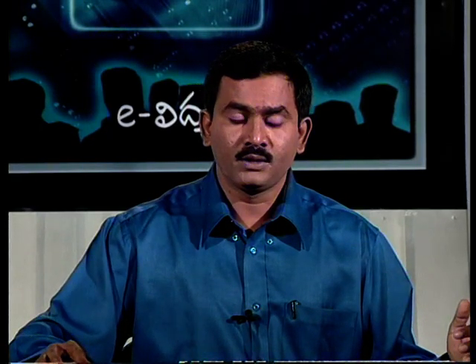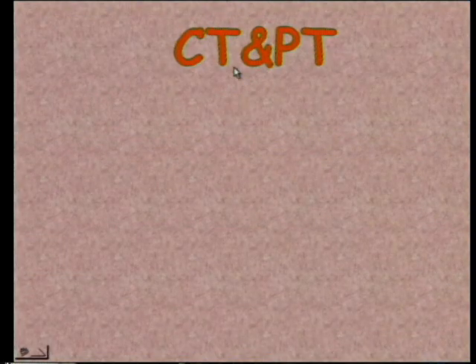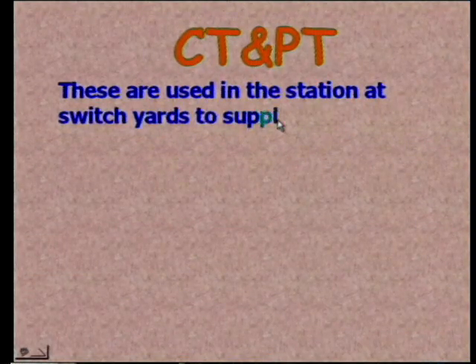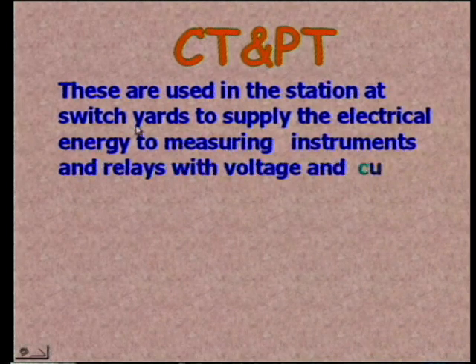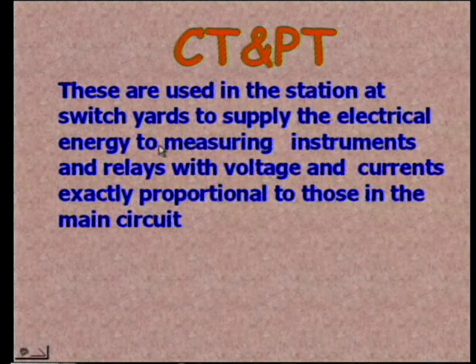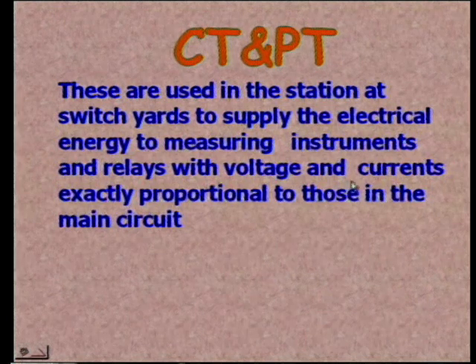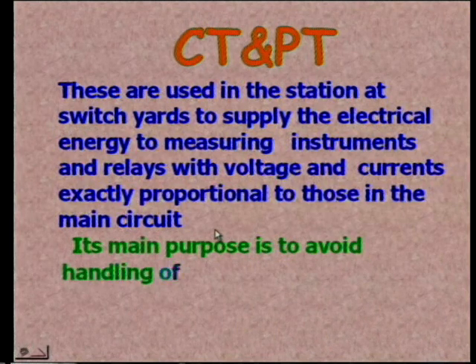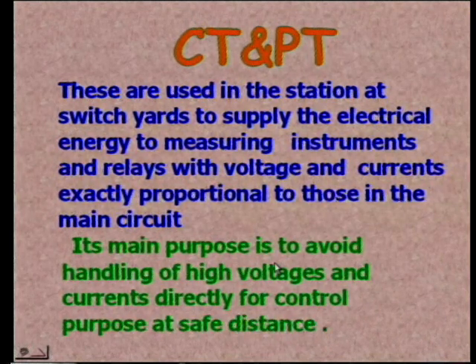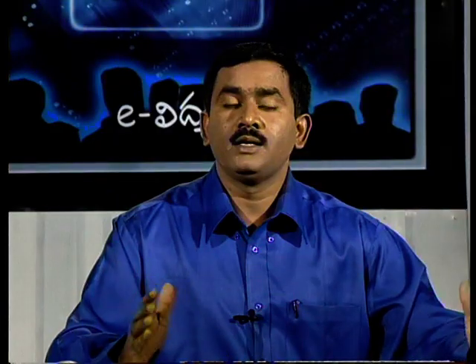So, you can see the instrument transformers. These are used in the station at switch yards to supply electrical energy to measuring instruments and relays with voltages and currents exactly proportional to those in the main circuit. Its main purpose is to avoid handling high voltages and currents directly, for control purposes at a safe distance. Now, it is a very interesting instrument, the CT and PT.